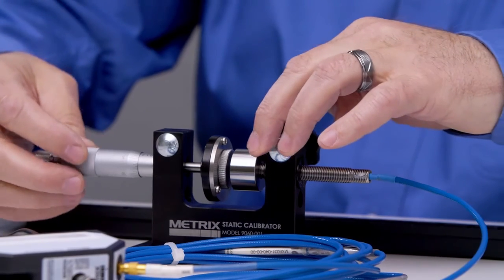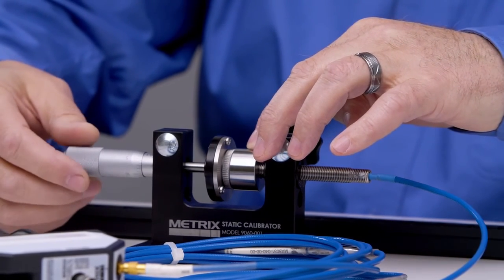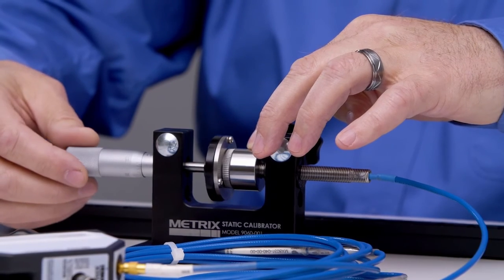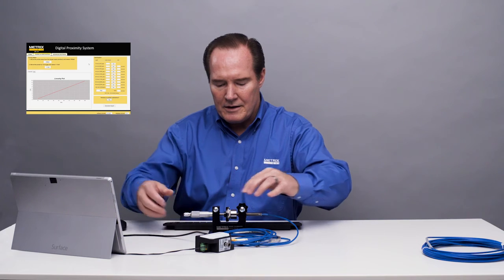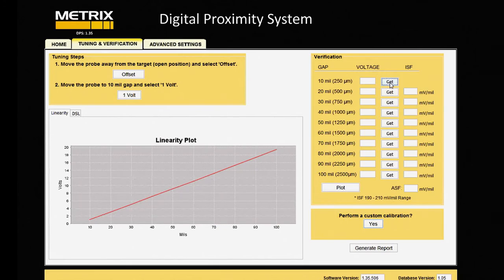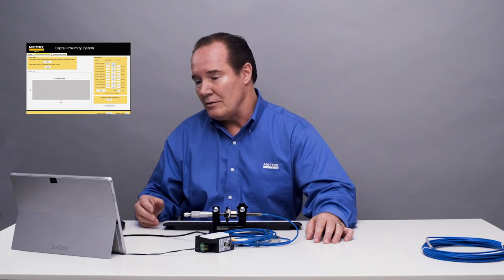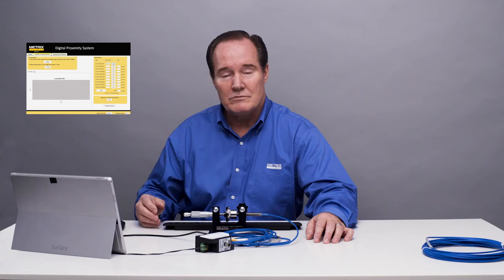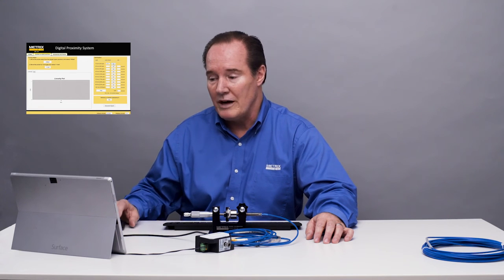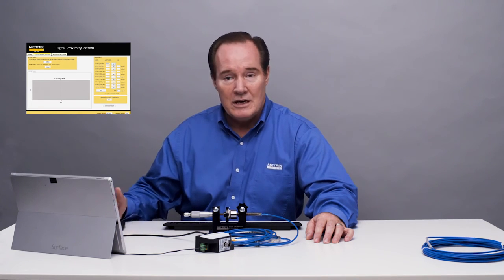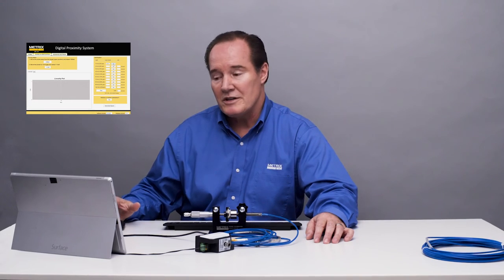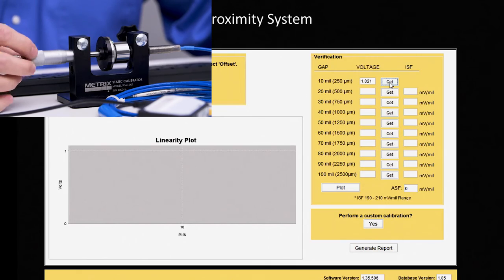So we'll go ahead and move the micrometer back to 10. We'll go to 0, verify we're still at 0. We're at 10, and we'll go ahead and say get. So it's now reconfigured because we did a custom calibration. And we have 1.021 volts, so that's good. Now we'll go ahead and do that every 10 mils, and we'll do what we've done before and just look at the results.